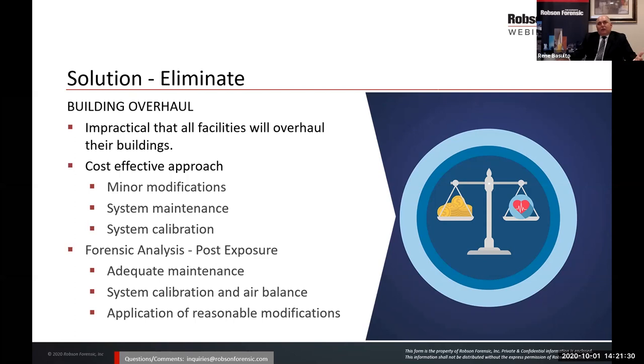When we look at it on a forensic approach, when we're analyzing a building post-exposure, we are going to look at these things. As a forensic engineer, I'm going to look at, was there adequate maintenance? Was the system properly calibrated? Was it balanced properly? Was there enough air going into the spaces that they needed to go into? We'll compare to the existing drawings or the original design and the design intent to see if it's being met, and whether any modifications were done to the system that are preventing the system or the equipment from achieving that. And we'll look at what reasonable modifications have been applied to the building.